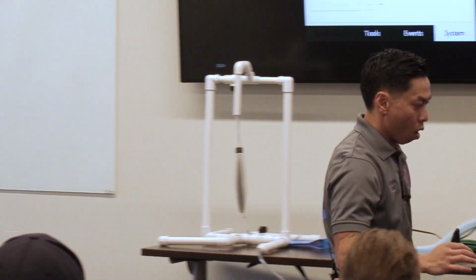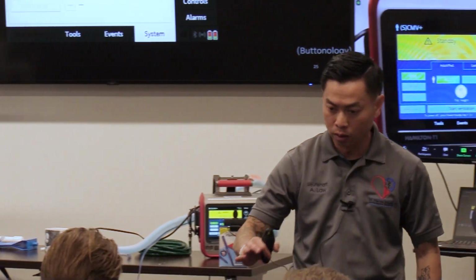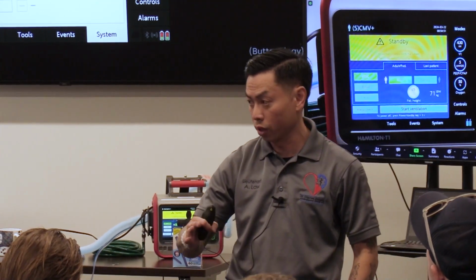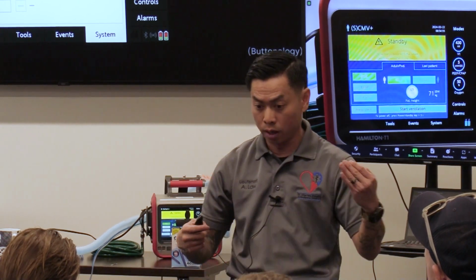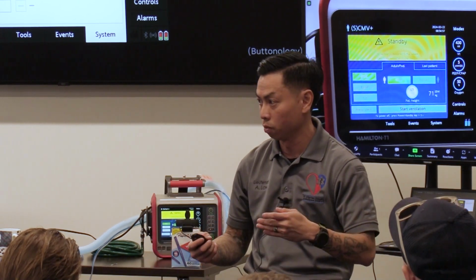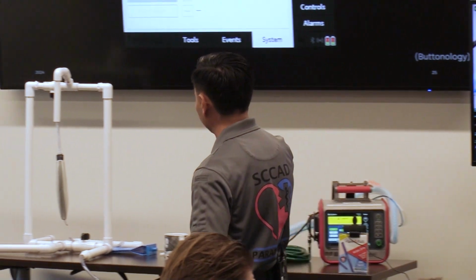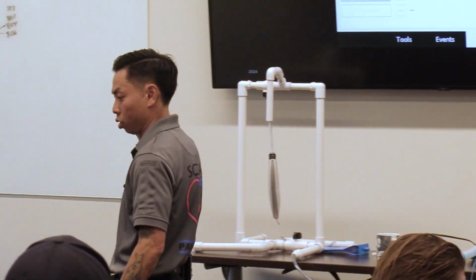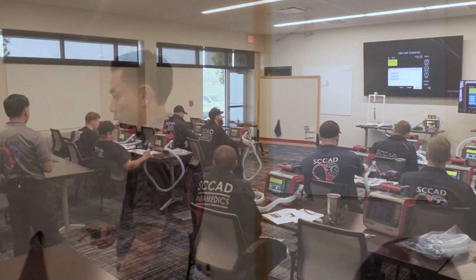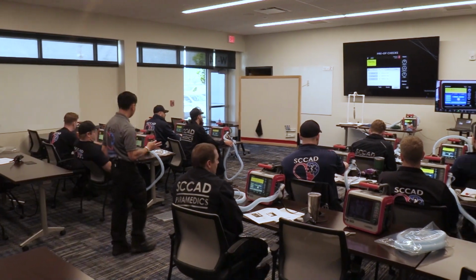I will say hardly ever when you're failing it is it a circuit problem. More than likely, when you're failing it, you're not performing the steps fast enough, or that diaphragm and that valve is messed up. So let's go ahead and start off with a leak test. And when you pass that, you can go ahead and go into the flow sensor test. All right, so everybody's passed the flow sensor and the leak test, right?